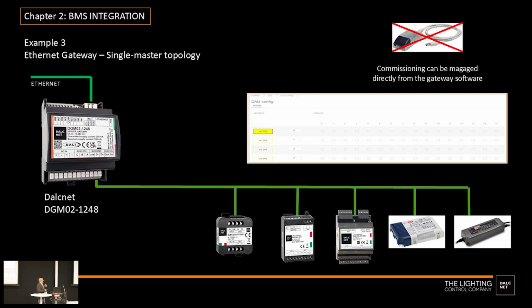Again, this integration has some difficulties, because when we speak about Ethernet, most of the time we're speaking about software, web interfaces, so it's not plug and play where you connect and it works. Sometimes there's work to be done on the PLC side, if there is a PLC, to adapt the protocol to the gateway. There are also complications based on the type of DALI commands you want to send.